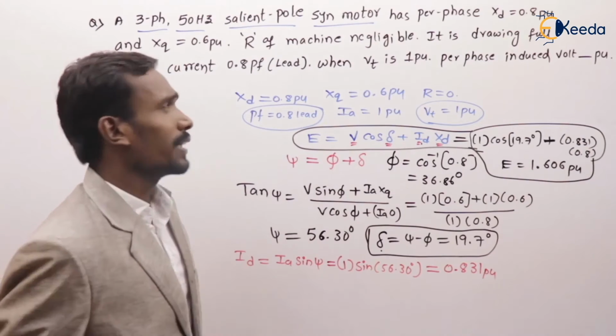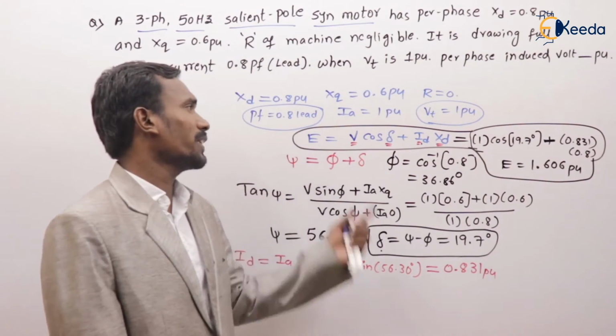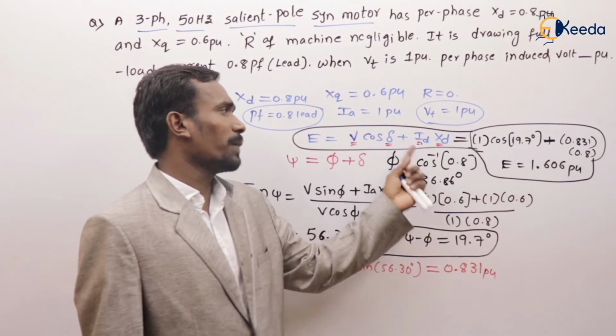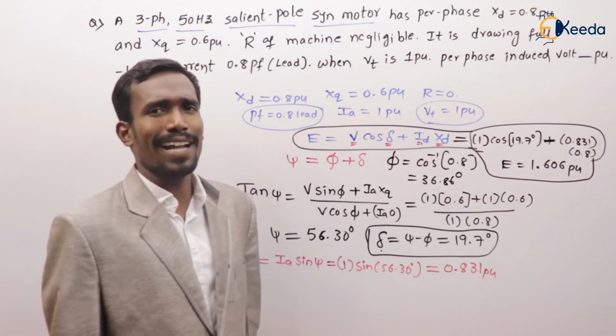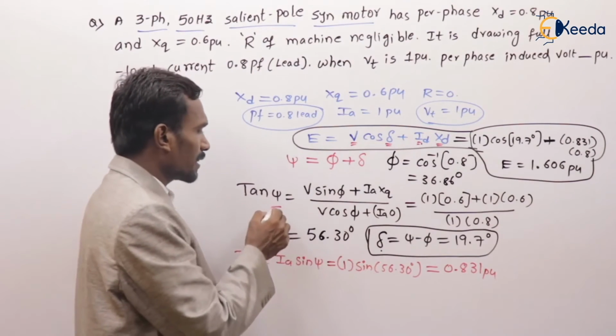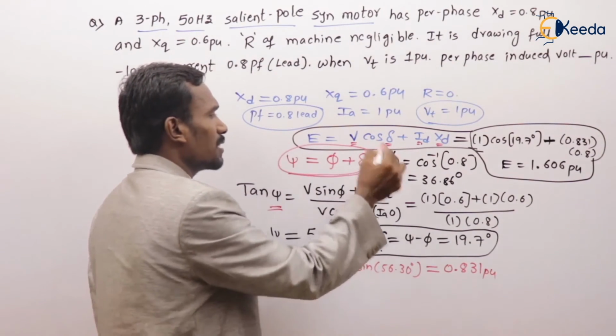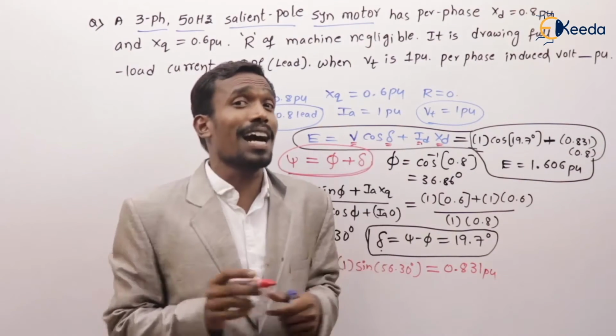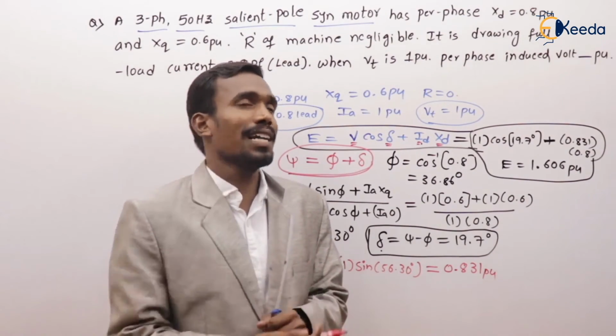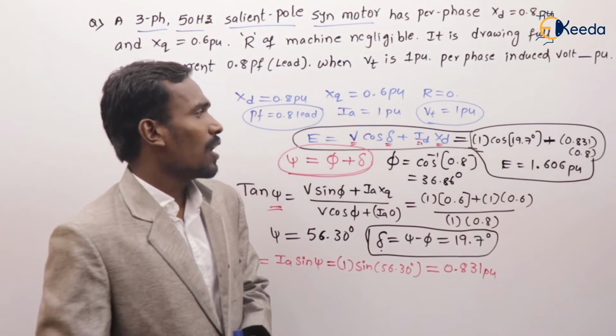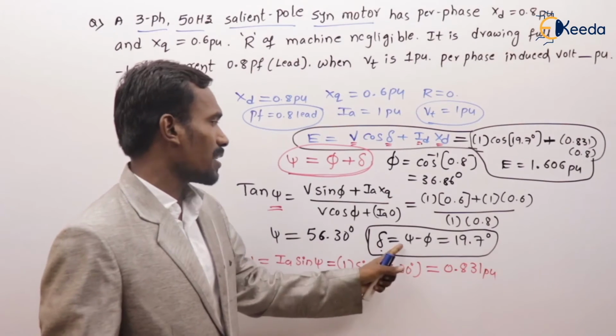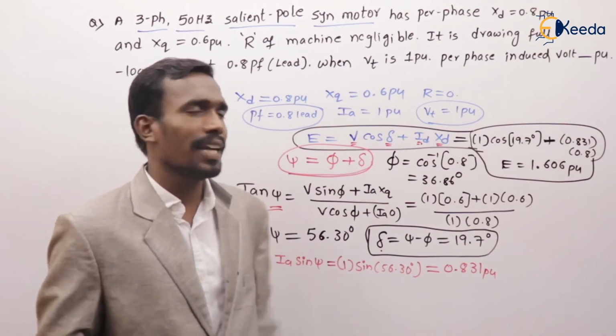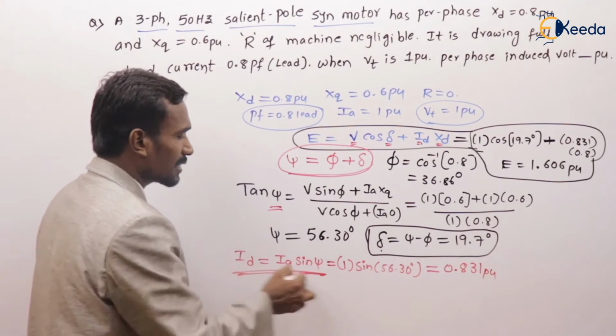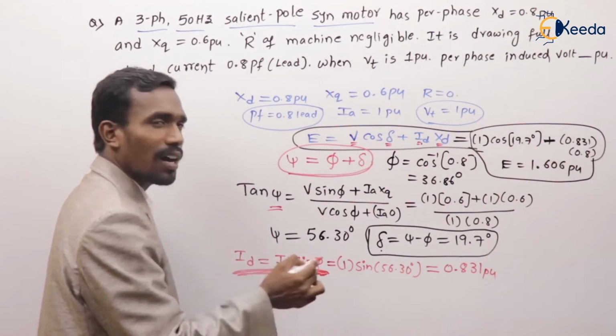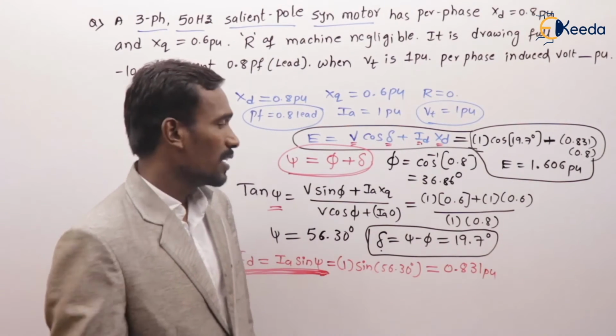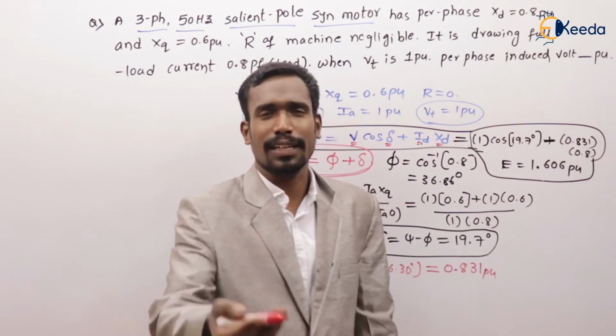In a salient pole machine, EMF equals V cos delta plus ID XD. For delta, I calculated psi. I have a formula: psi equals phi plus delta for a motor. Then I calculated the value, and I calculated delta. Then I calculated ID, where ID equals IA sin psi. Then substitute all those values, and we can get the answer.